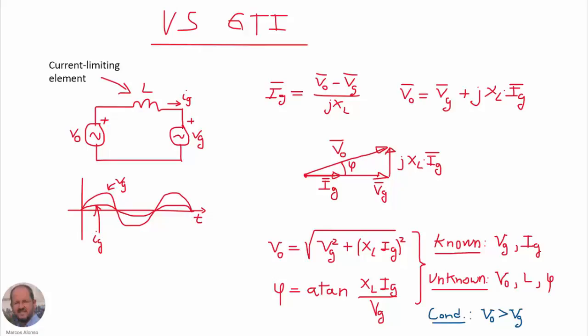In this video, we focus on the voltage source grid-tied inverter. Let's see how to inject current into the grid using a voltage source. The inverter behaves like a voltage source at the output, and the grid voltage is another voltage source. We cannot connect them in parallel because the current will not be limited, so we need some element to limit the current. We could use a resistor, a capacitor, or an inductor. A resistor is not a good solution due to losses. The best possibility is to use an inductor, because the inductor will also serve to filter high-frequency harmonics.